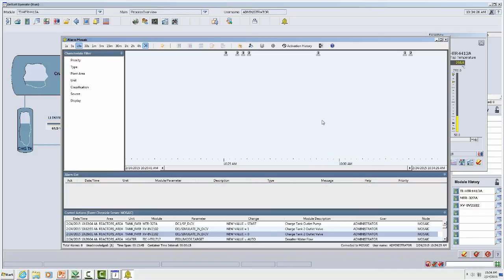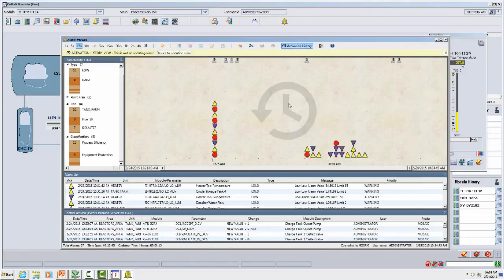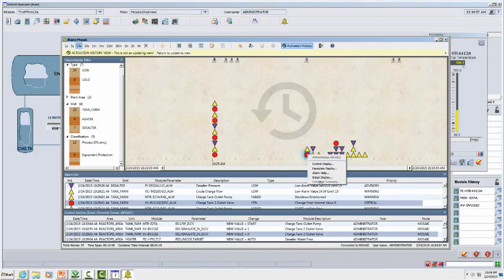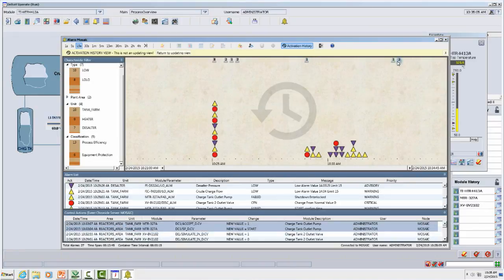Our alarm flood is over. Project yourself in time to the shift transition that's going to occur a couple hours down the road. You want to explain to your supervisor and the incoming operator what you observed during your shift. Alarm Mosaic provides an activation history view that makes that task easy. What we're seeing here are the alarms reconstructed from events automatically recorded in the DeltaV system, complete with the ability to look at alarm help, look at things that might have caused it, and discuss the control actions taken to resolve the problem.